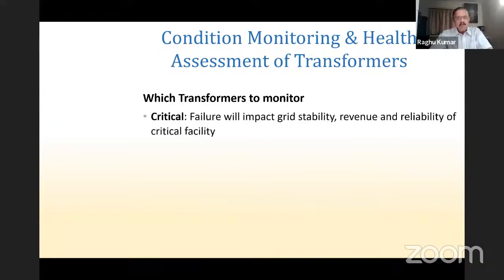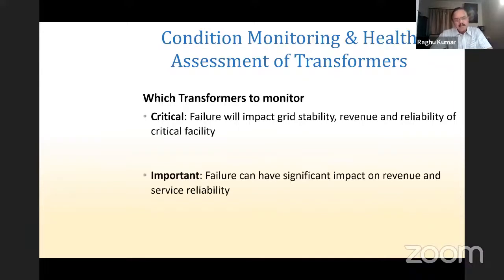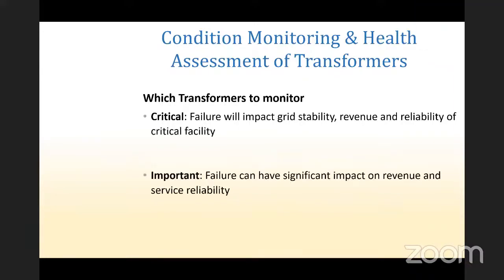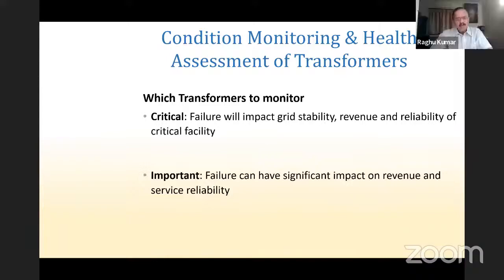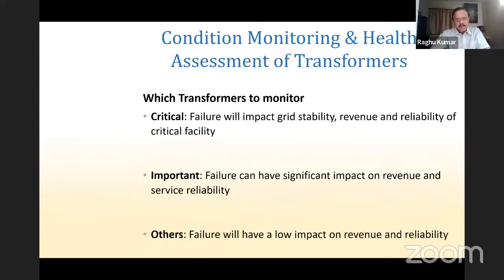So what we are doing is, we are dividing the transformers into 3 different categories. The one is the critical transformers. The failure of the critical transformers can impact grid stability, and it will be a major revenue loss in case of a failure. The second set is important transformers. The failure can have significant impact on the revenue. Normally, interbus transformers come into this class. Next is the unimportant transformers. The failures are low impact.